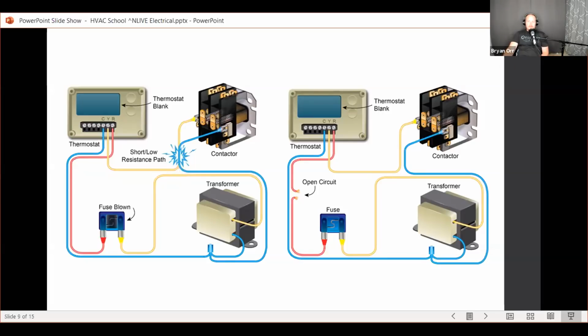Now, Kevin says, wouldn't that be a shunt, not a short? That may be a better way of saying it. Either way, it's an undesigned connection. I've heard it called a short quite often. Caleb says it's a short. I don't know, it's just what I've always called it. So I always just say it's an undesigned low resistance path. When you have a path between two things that aren't designed to have a path between them, to me, that's a short. Now, an overcurrent that's associated with a short, that's what blows your fuse.